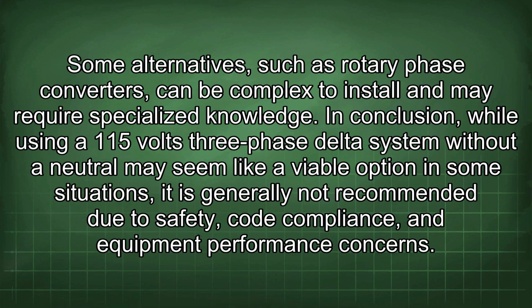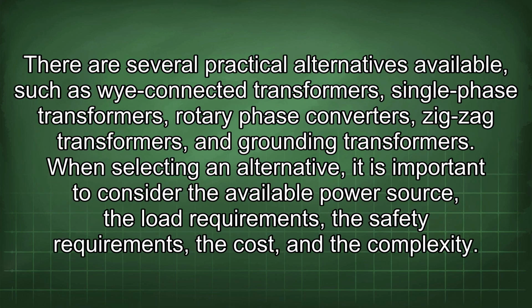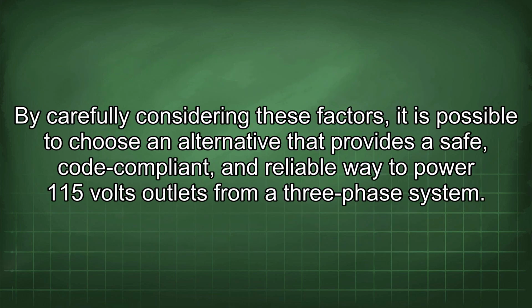In conclusion, while using a 115 volts three-phase delta system without a neutral may seem like a viable option in some situations, it is generally not recommended due to safety, code compliance, and equipment performance concerns. There are several practical alternatives available, such as Y-connected transformers, single-phase transformers, rotary phase converters, zigzag transformers, and grounding transformers. When selecting an alternative, it is important to consider the available power source, the load requirements, the safety requirements, the cost, and the complexity. By carefully considering these factors, it is possible to choose an alternative that provides a safe, code-compliant, and reliable way to power 115 volts outlets from a three-phase system.